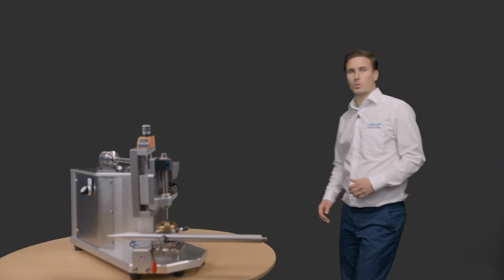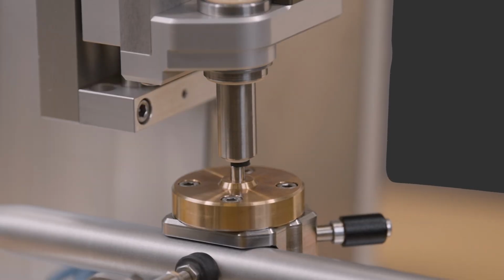At Kistler, we use a pressure pulse system such as this one. With it, we can calibrate our 601, 603C, and 6233B sensors, as well as other mounting compatible solutions. The system generates a pulse between 2 and 10 milliseconds. This allows an accurate calibration of these sensors by drastically shortening the measuring time compared to other established quasi-static calibration systems. We have found shorter pulses to introduce new sources of errors.